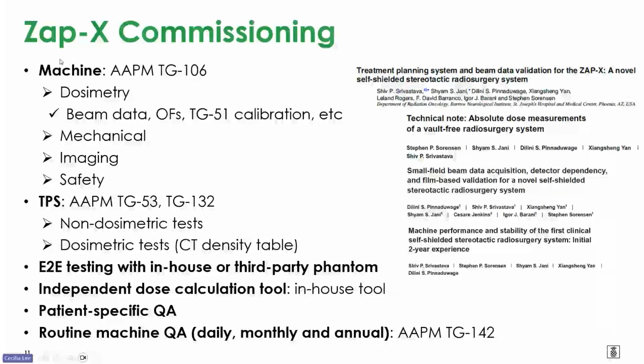So commissioning can be pretty extensive, but not too different from any commissioning for any other LINAC. You have a machine component and a TPS component. A big thing is you have to collect the data: beam data, PDD, and profile, and then you measure output factor, and you calibrate output in TG51 calibration. Then you still need to measure some other things that acceptance testing didn't cover, mechanical, imaging, and safety.